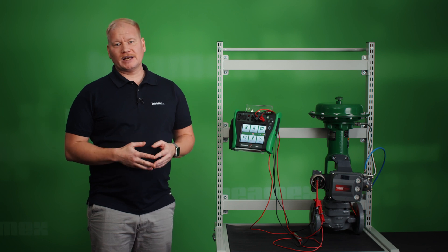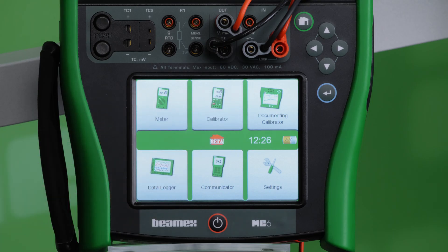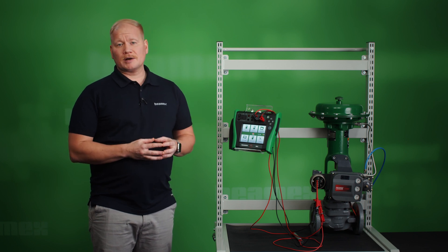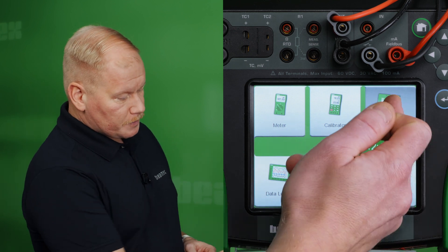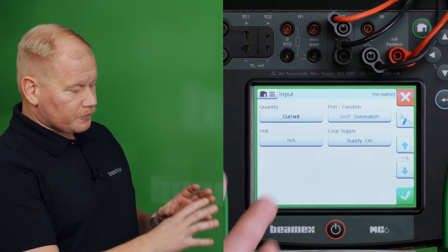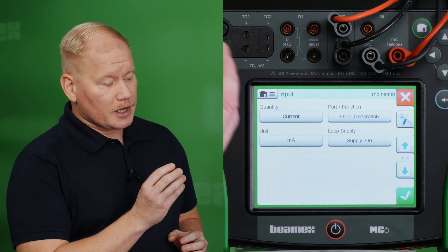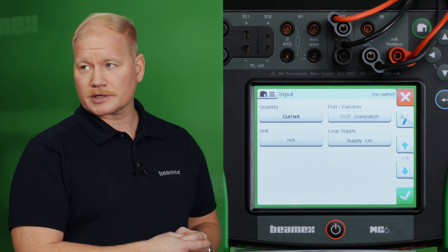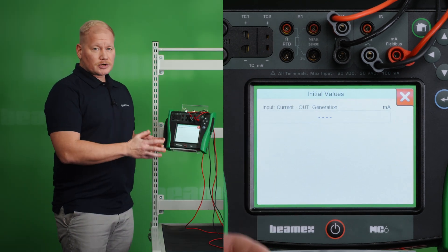Now we are ready to continue to the linearity test. I will perform the automatic linearity test using the MC6 documenting calibrator mode. Before I go any further I need to have the instrument established in the calibrator. I can either have it sent over from CMX calibration management software or I can create it straight in the MC6, and that's what I'm going to do now. So I go to the documenting calibrator, create new instrument, and for the input signal the current generation — current is already chosen. But at the moment there's 0mA being generated, meaning the valve is not powered up, so I go to menu and choose initial values and enter anything above 4mA.